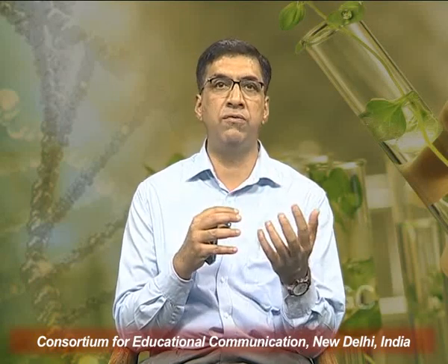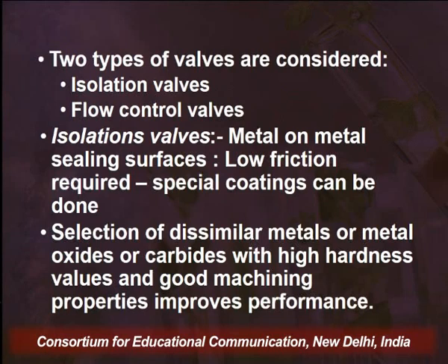Now coming back to the valves that are used in the supercritical fluid unit, depending upon their usage, their effect, we have isolation valves and the flow control valves. Isolation valves are to stop the flow, to cut off one of the vessels, as we discussed in the industrial setup of a supercritical fluid unit, whereas the flow control valves are used to maintain the flow rate of the solvent. If we look into the structure of the isolation valves, they have a metal sealing surface, and therefore whatever metal we are using, it should be able to withstand the pressure and temperature condition. Further, that metal should have a very low coefficient of friction, because we cannot use lubricants in such kind of extraction units.